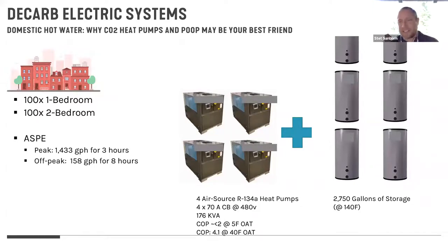And I want to point out something that's very important if you're looking at decarbonization and electrifying your buildings, and that's your connected load. I typically can find space for heat pumps and storage in our projects, either in the parking garage or below grade. Actually, in a cold climate, that works out great because you've got that ground-coupled heat exchange by default, so it can temper the air temperature really nicely. But the bigger issue that we actually see is the increase on the load that your transformer is going to see. And that is a big-ticket item, especially in retrofits.